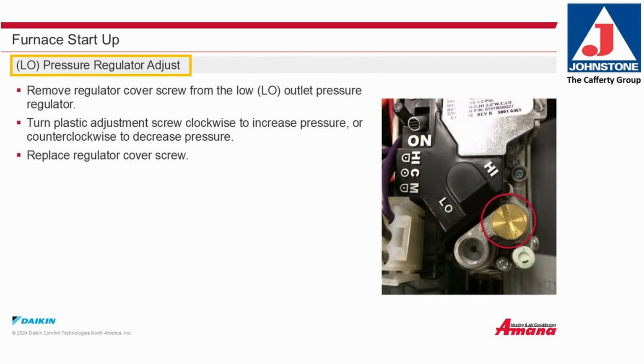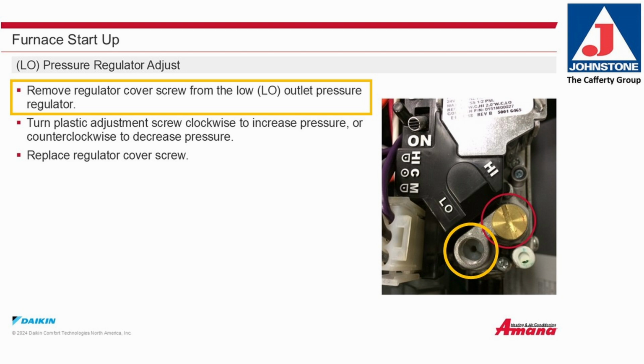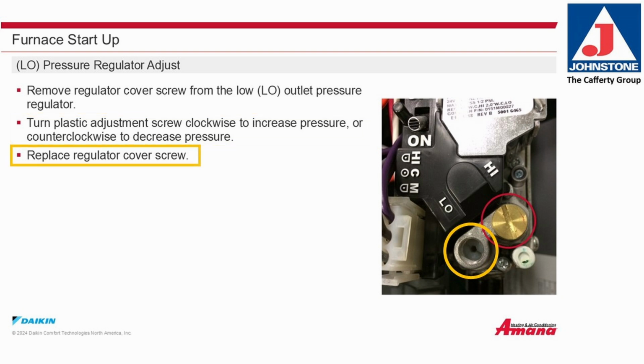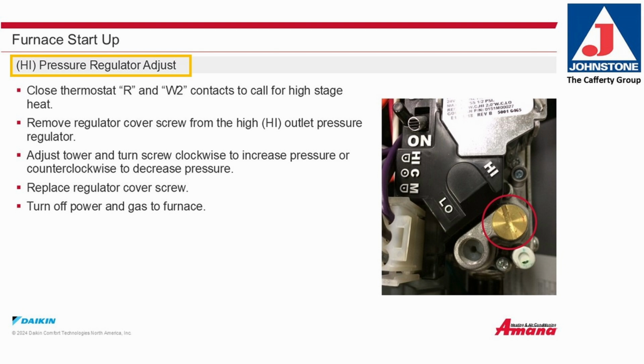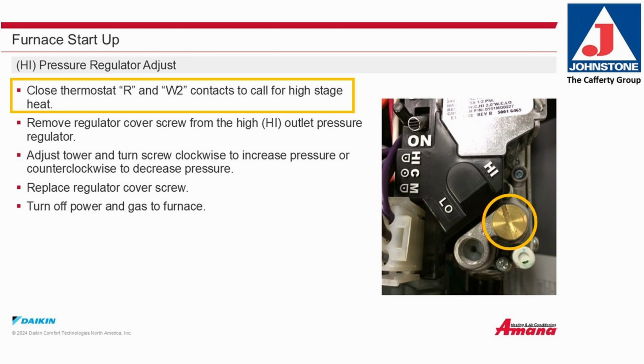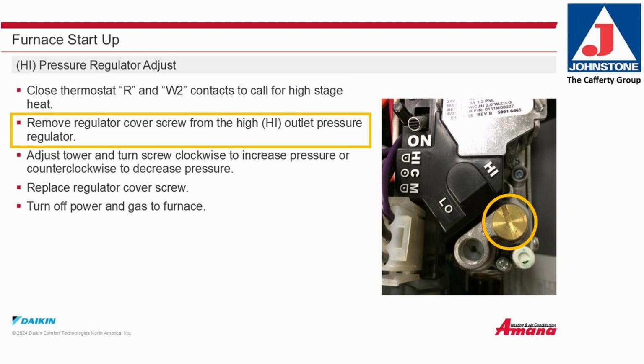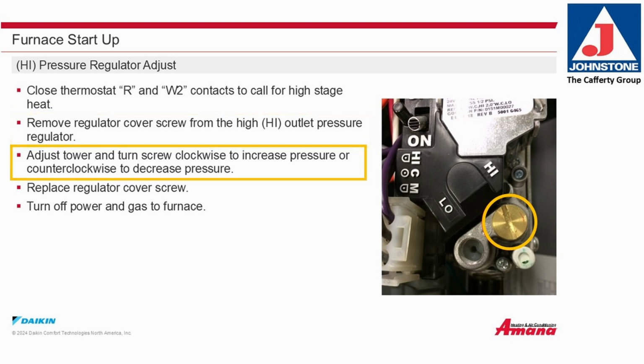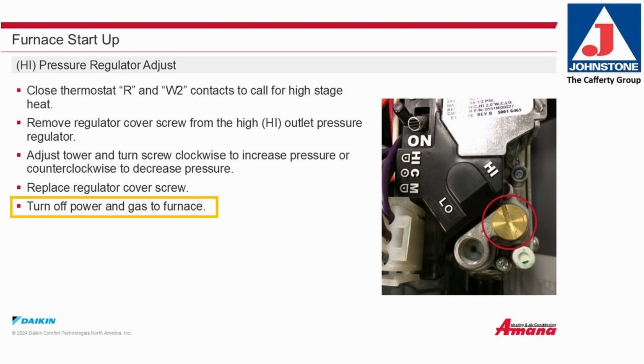Low pressure regulator adjustment. Remove the regulator cover screw from the low outlet pressure regulator. Turn the plastic adjustment screw clockwise to increase pressure or counterclockwise to decrease pressure. Replace the regulator cover screw. High pressure regulator adjustment. Close the thermostat R and W2 contacts to call for high stage heat. Remove the regulator cover screw from the high outlet pressure regulator. Turn the screw clockwise to increase pressure or counterclockwise to decrease pressure. Replace the regulator screw. Turn off power and gas to the furnace.